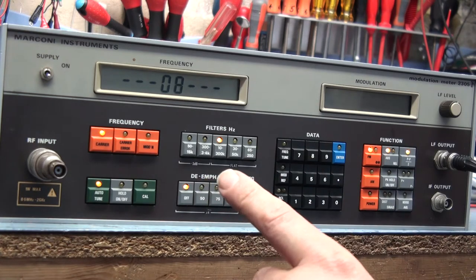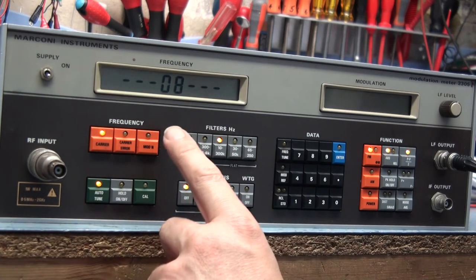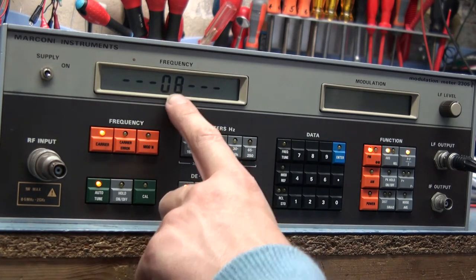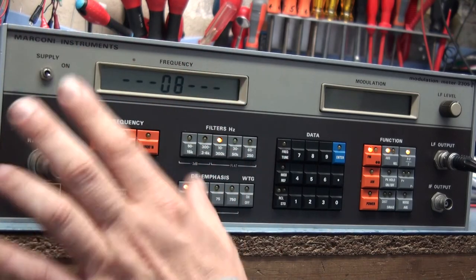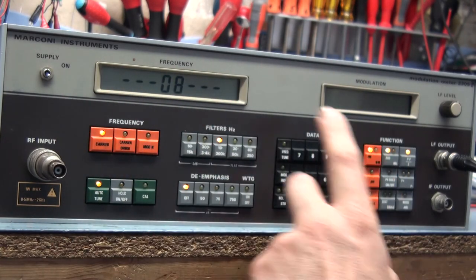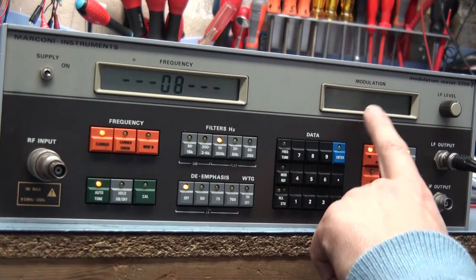Now it's just passed the calibration but it's come up with this error message. Usually it will say pass. Anyway, you put an RF signal in and it will show up the correct signal. And if you select FM modulation and modulate with one of the signal generators it will come up with the correct modulation.